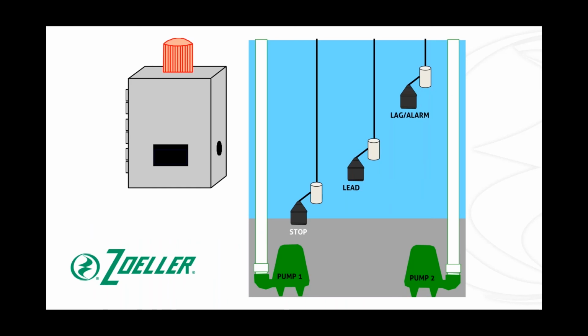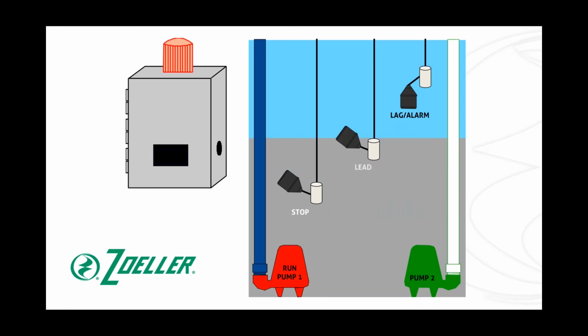So you can see that we have a duplex panel here. We have 2 pumps down in the pit, and we have 3 weighted float switches here. So to begin, we're going to have some water start coming into the pit. As the water comes in, you're going to see now the stop float has risen. Water continues to come into the pit, and now our start float, or what we're referring to as the lead float switch, is activated.